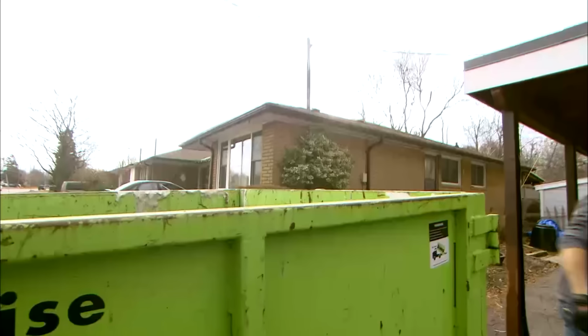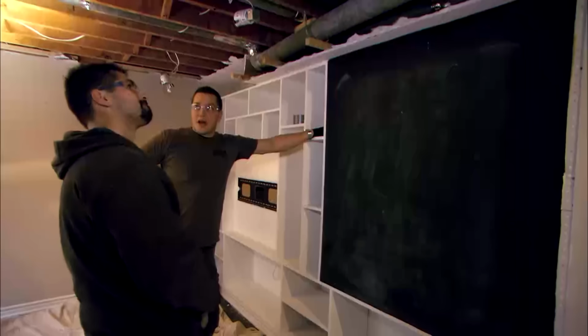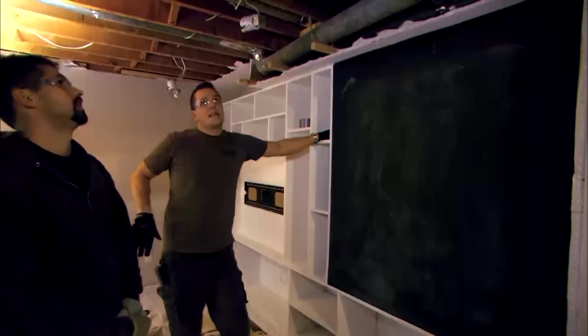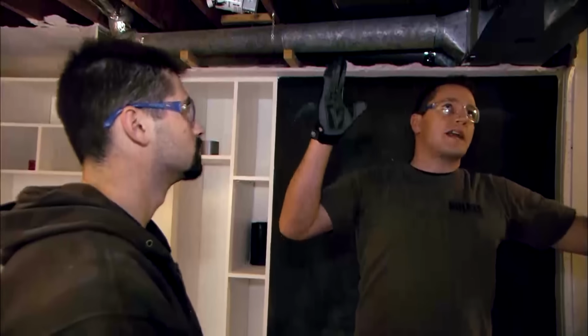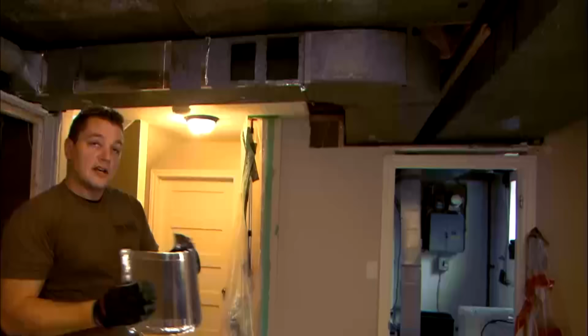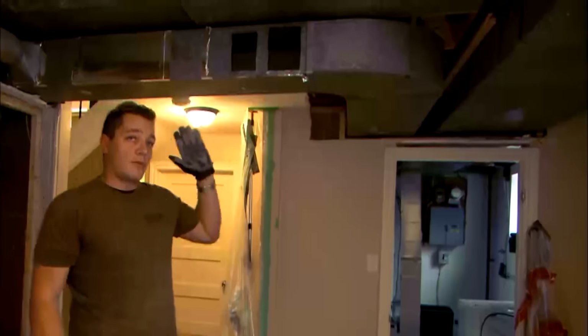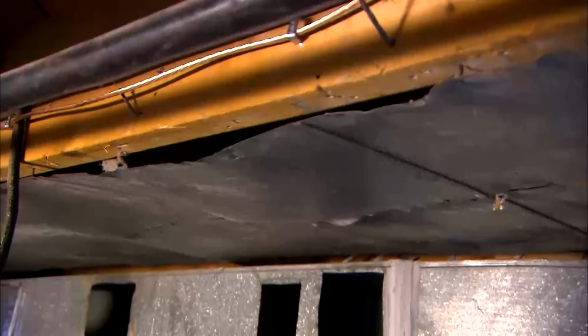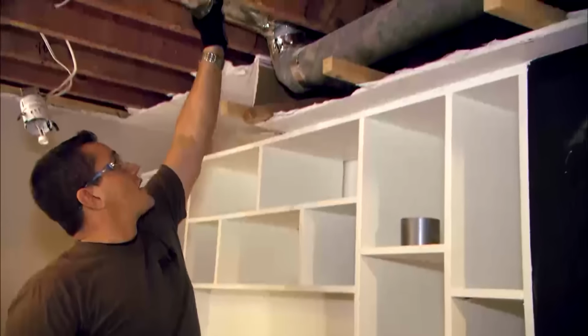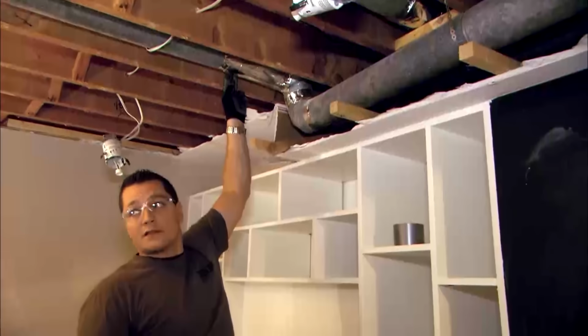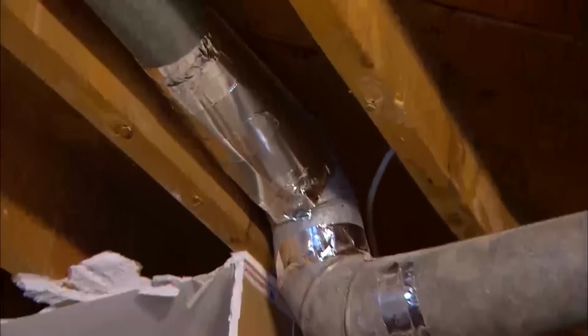So what did I find wrong here? Almost everything. I can tell you right now this was not done by someone in HVAC. You look at things like this — this is why Mike was seeing the big heat source right here, because this was just flopping open. Not the proper gauge metal, not the proper way to do it. They're getting major heat loss in this house. They slapped together made-up ductwork right here. This isn't even real ductwork — they basically cut a piece of duct and taped it together.